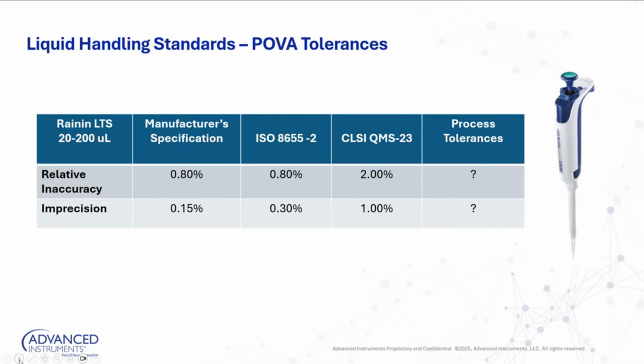So Rainin has said that if you're testing at 200 microliters, the relative inaccuracy is plus or minus 0.8%, and imprecision is 0.15%. Those are really tight tolerances. When you take a look at ISO 8655 Part 2's table of permissible errors, they align nicely with regards to inaccuracy. They also indicate plus or minus 0.8%, but their imprecision is a little bit broader than Rainin's, at 0.3%.